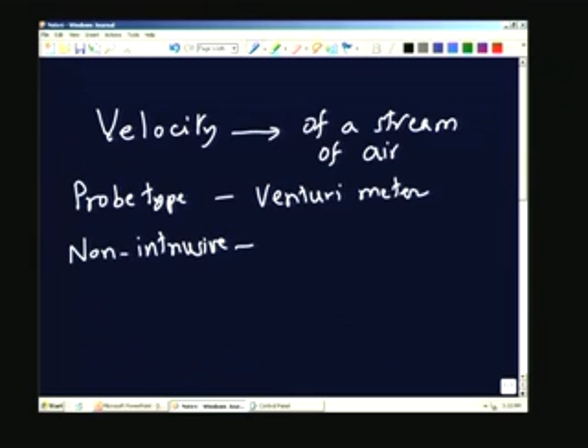So the Venturi meter is a probe type one, because it deliberately introduces a change in the cross sectional area, and therefore a change in velocity. We are not measuring the velocity which exists originally, but trying to modify the velocity to increase it and then measure it.